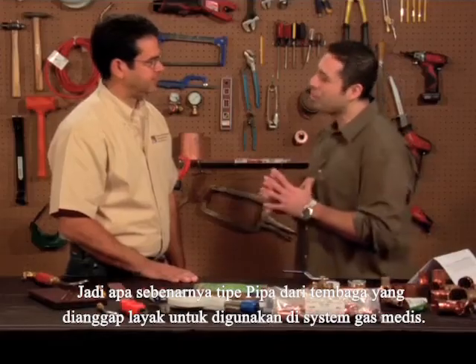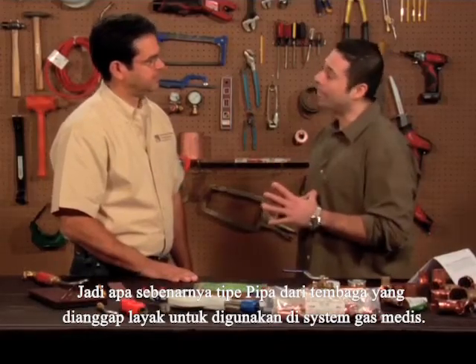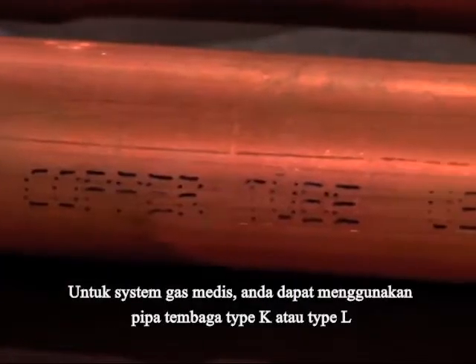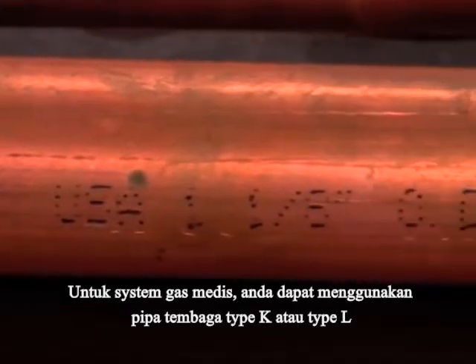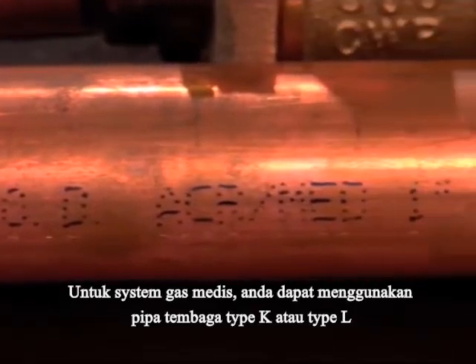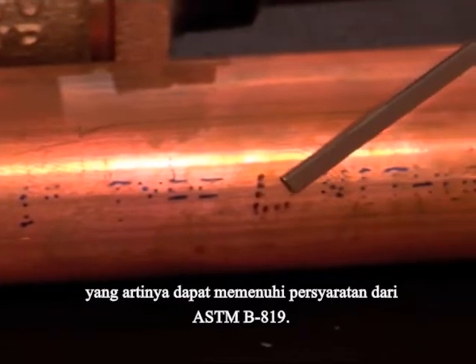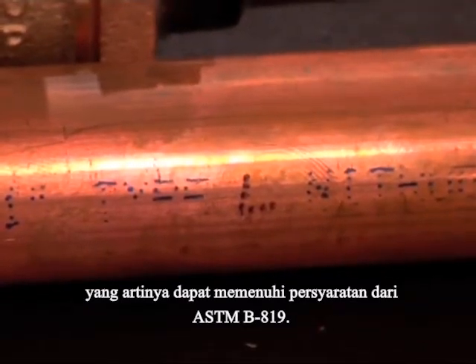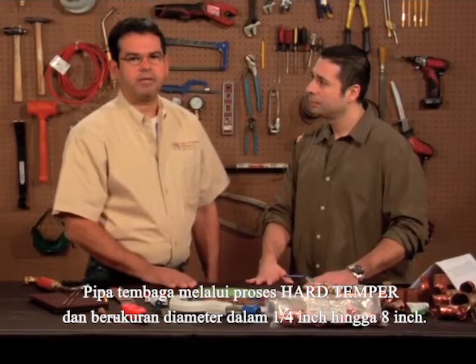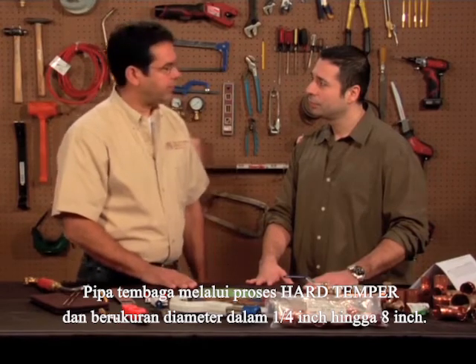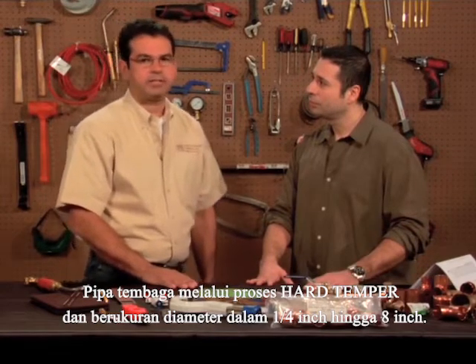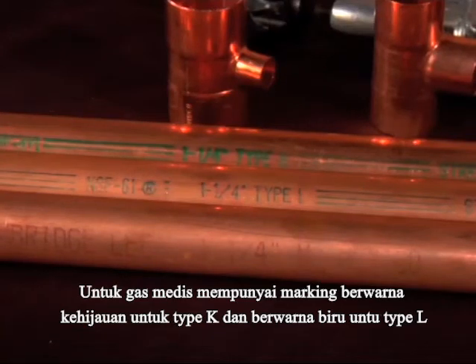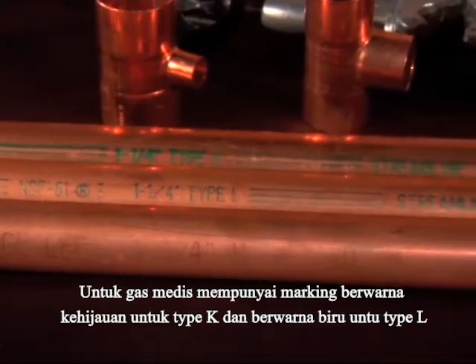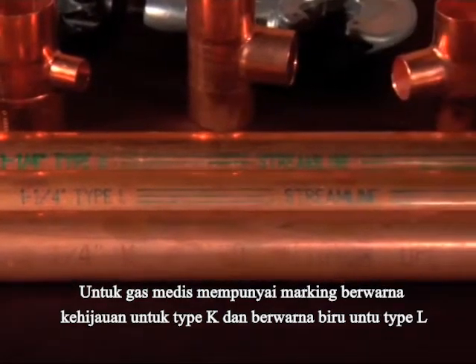So what types of copper tube are acceptable for medical gas systems? For medical gas systems, you can use copper tube, either type K or type L, meeting the requirements of ASTM B819. The copper tube must be hard tempered and from 1/4 inch in size to 8 inch in size. Medical gas tube will have green markings for type K and blue markings for type L.